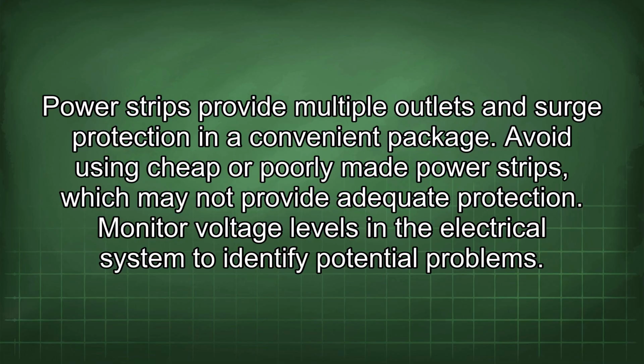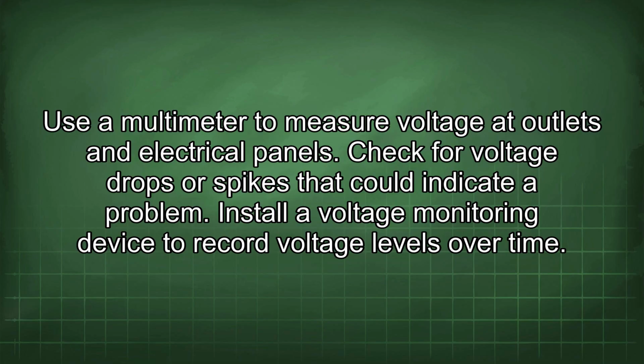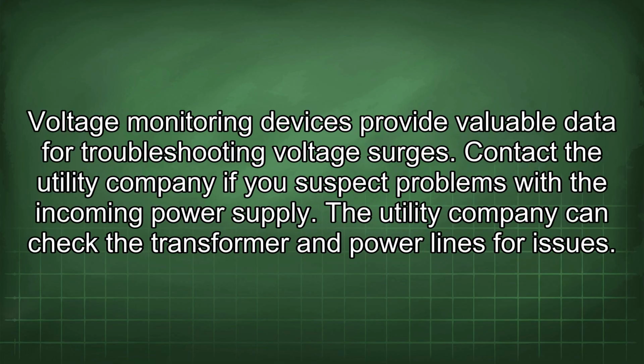Monitor voltage levels in the electrical system to identify potential problems. Use a multimeter to measure voltage at outlets and electrical panels. Check for voltage drops or spikes that could indicate a problem. Install a voltage monitoring device to record voltage levels over time. Voltage monitoring devices provide valuable data for troubleshooting voltage surges.